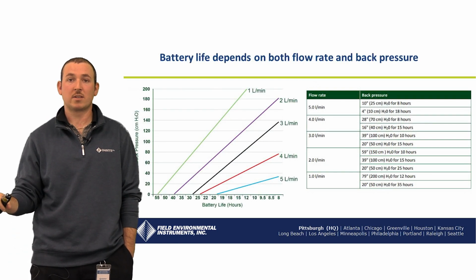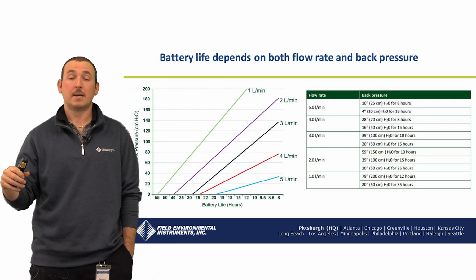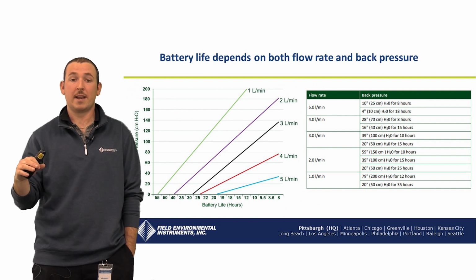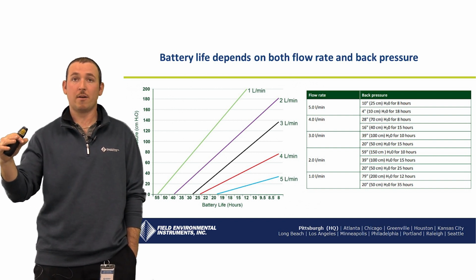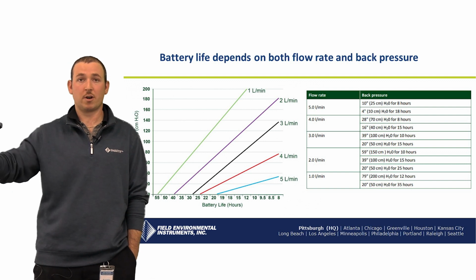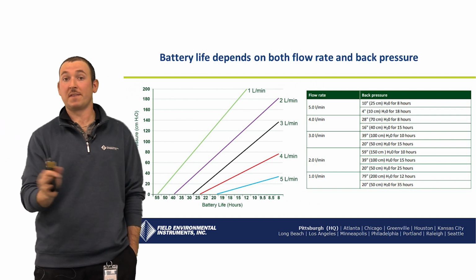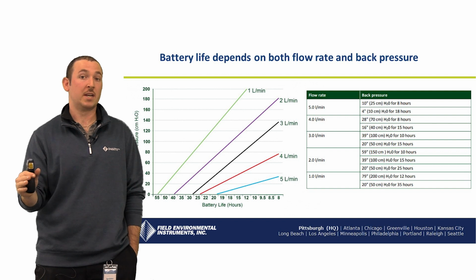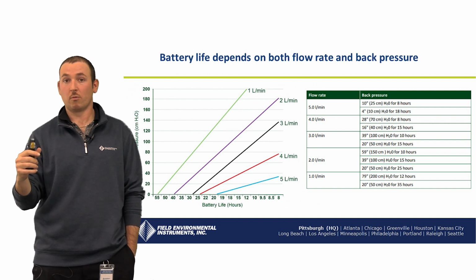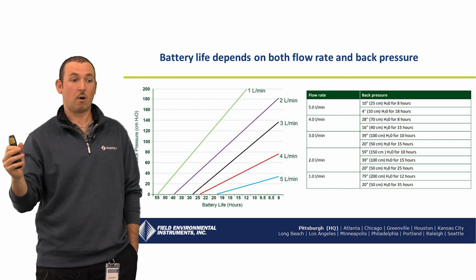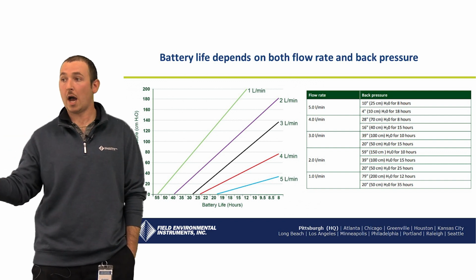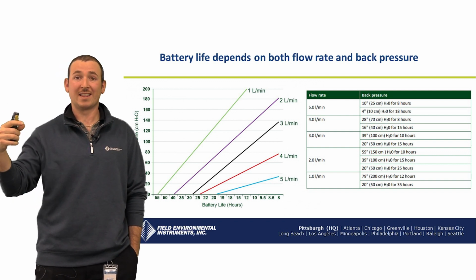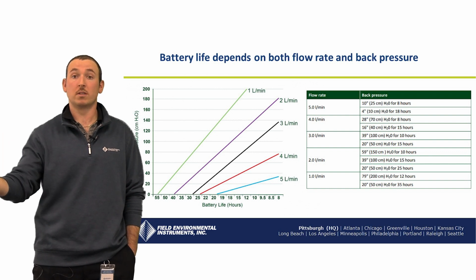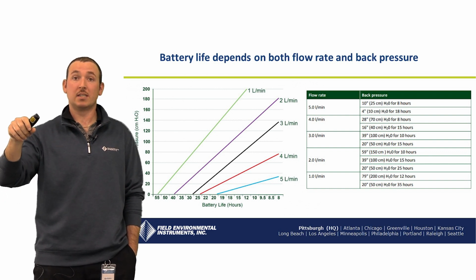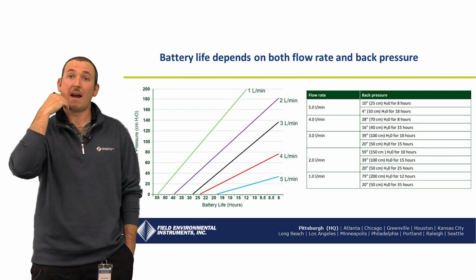So when it comes to the battery life of the Apex 2, it's pretty robust. In fact, Casella says that in perfect conditions at the lowest flow rate and no back pressure at all, the battery should last over 50 hours. But that's perfect conditions. We all live in the real world where that's never going to happen. You might be outside where it's freezing cold or too hot. You've got filters running in line. You might be running duplicates, who knows?